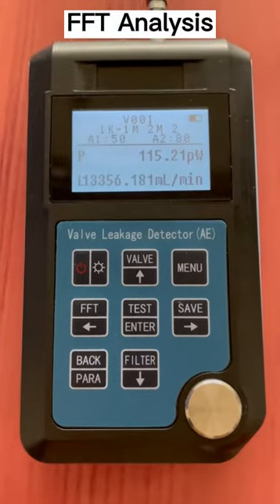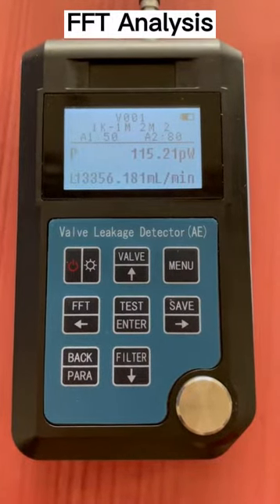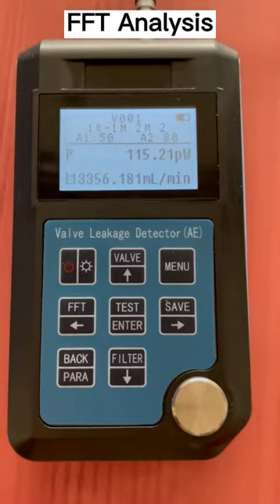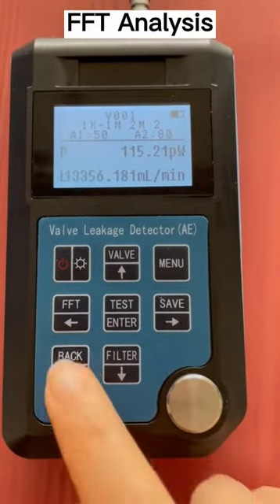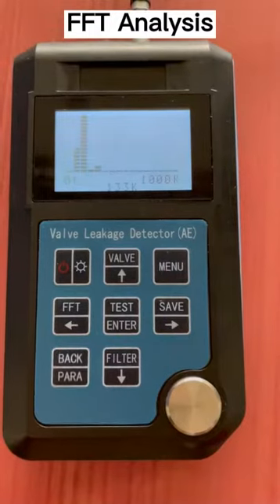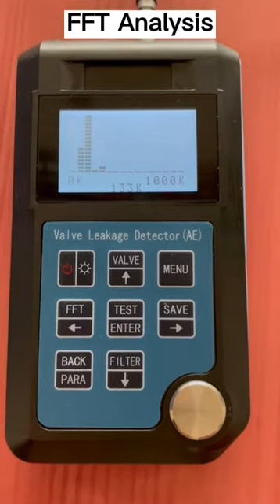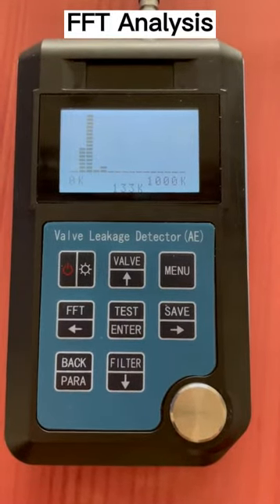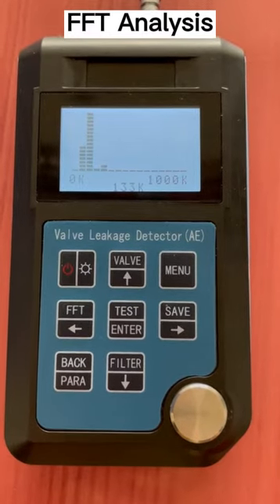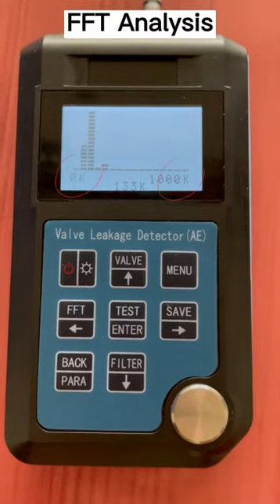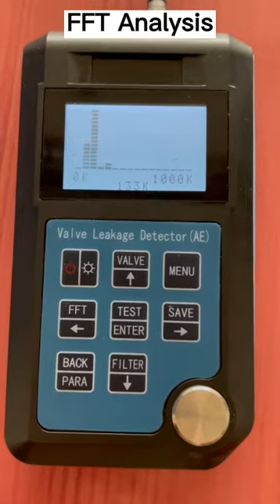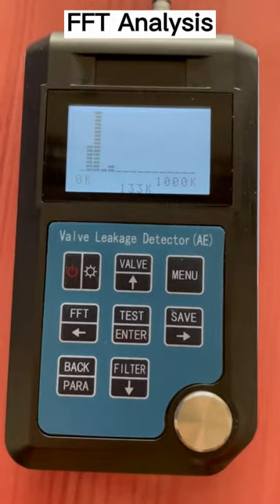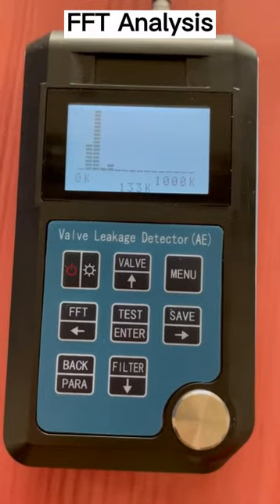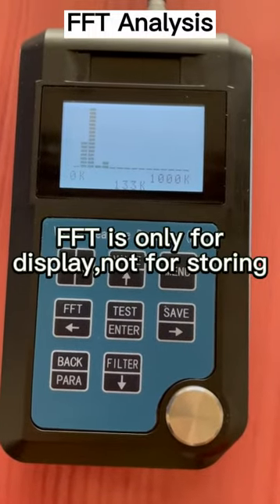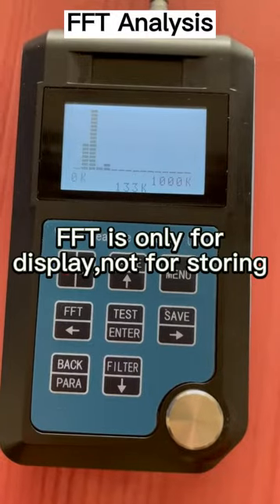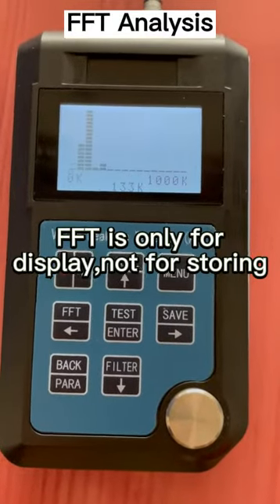The device can process the current test result for FFT analysis. In the test mode, press the FFT key to enter the FFT page. The maximum of the y-axis is based on the maximum values of the spectrum. The two values on the x-axis are the two frequency boundaries. The value in the middle bottom is the peak frequency. Please note that the FFT results are only for display, not for storing.